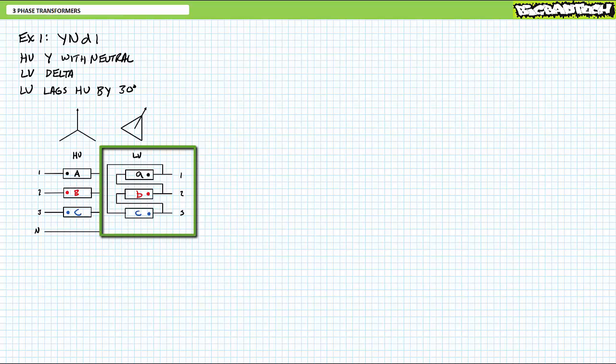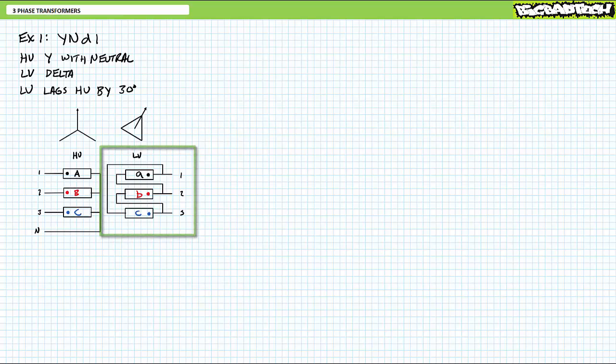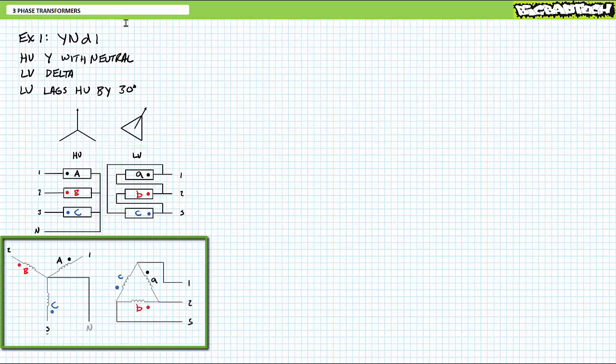A YNd1 configuration looks like this: A no-dot to B dot, B no-dot to C dot, C no-dot back to A dot — A to B to C back to A. If you were to expand this out for a schematic, the YN-configured high-voltage side would look like this with all non-dotted ends tied together, and the delta-configured low-voltage side would look like this — A no-dot to B dot, B no-dot to C dot, C no-dot back to A dot — with lower winding lowercase a between lines one and two, lowercase b between lines two and three, and lowercase c between lines three and one.